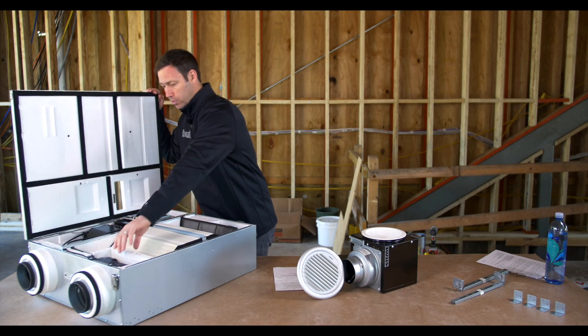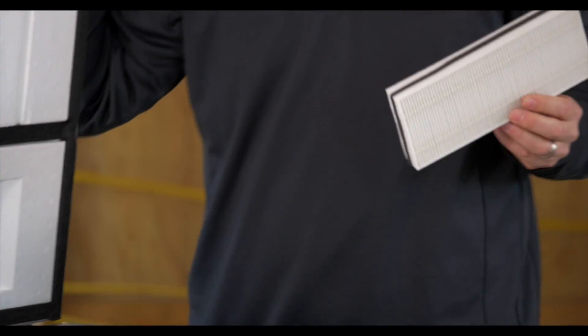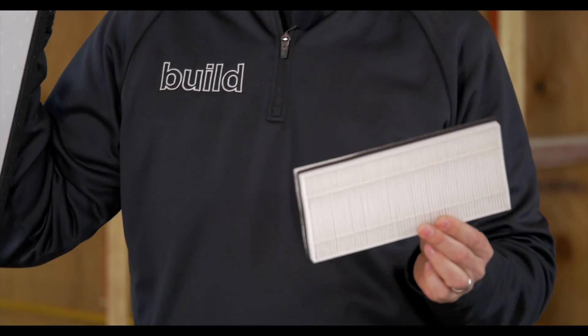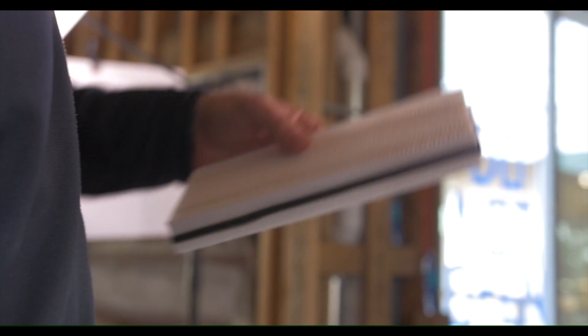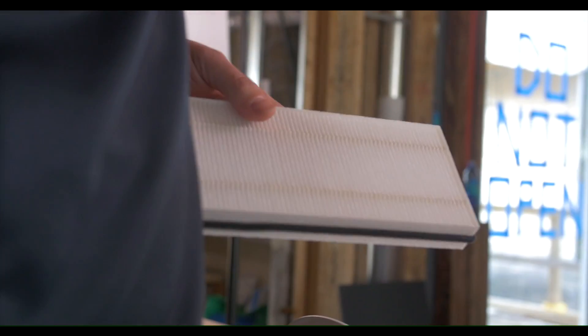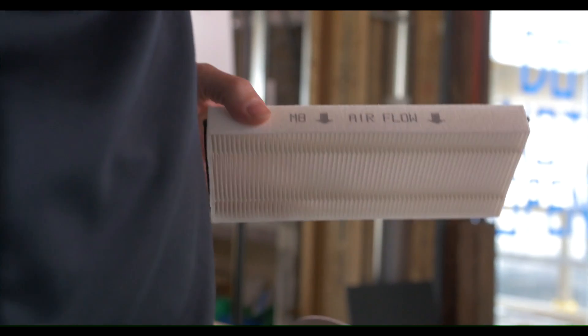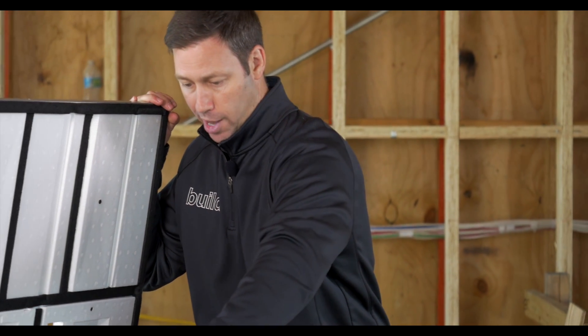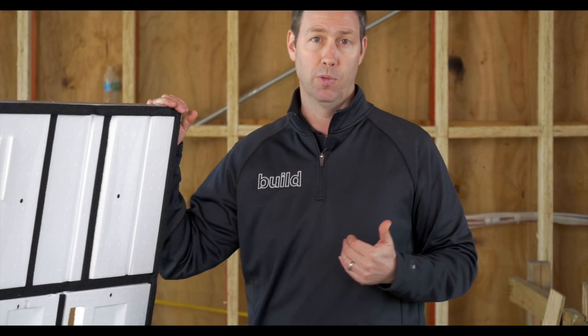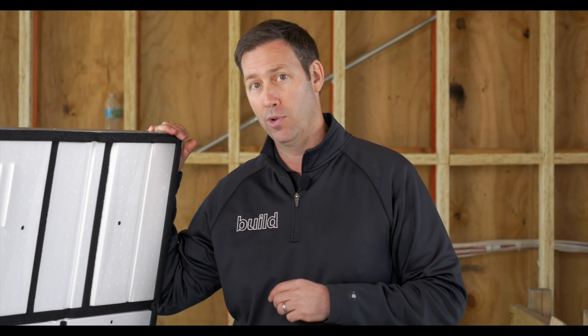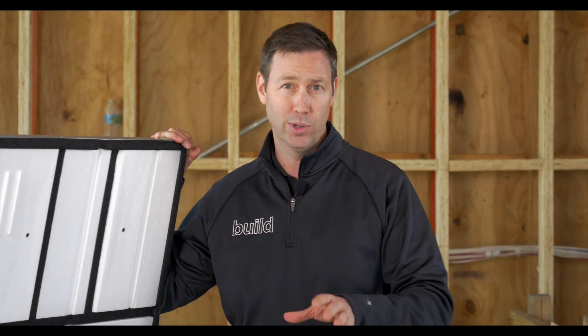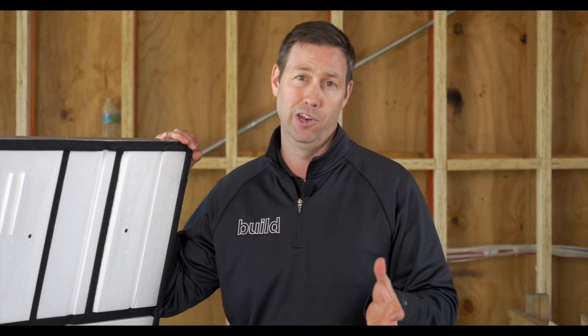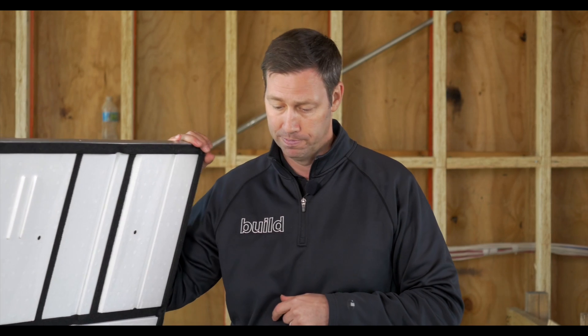Here's one thing that really separates this unit though from others that I've seen and I was really excited when I saw this. This has a very nice filtration system. Comes standard with a MERV8 filter right here. Super easy to get to. We can clean that out with a vacuum every 90 days or we can replace it and we can actually upgrade to MERV13 filtration. That's unheard of in an ERV.